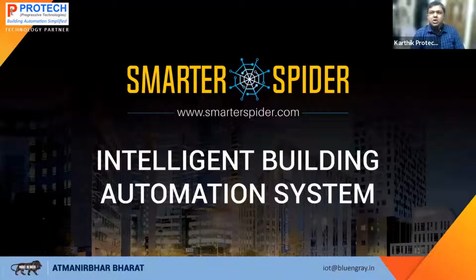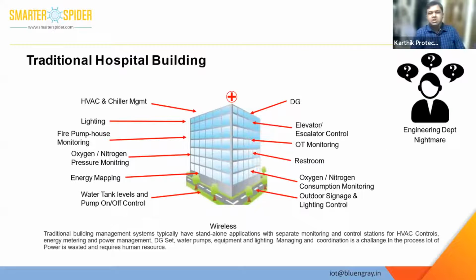So through our system, we not only help our clients in monitoring and controlling all the utilities, but also help them in energy savings. Now, when it comes to a traditional hospital building, we have multiple utilities such as HVAC and chiller management, lighting, fire pump monitoring, oxygen or nitrogen pressure monitoring, energy mapping, water tank levels and pump on-off control, DG monitoring, elevator escalator on-off control, then OT monitoring, restroom monitoring, oxygen or nitrogen consumption monitoring, and then outdoor signage and lighting control.